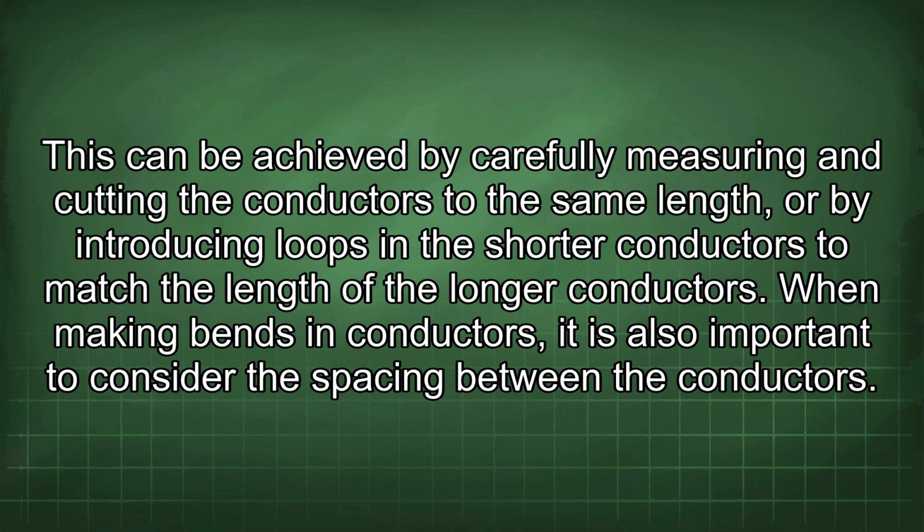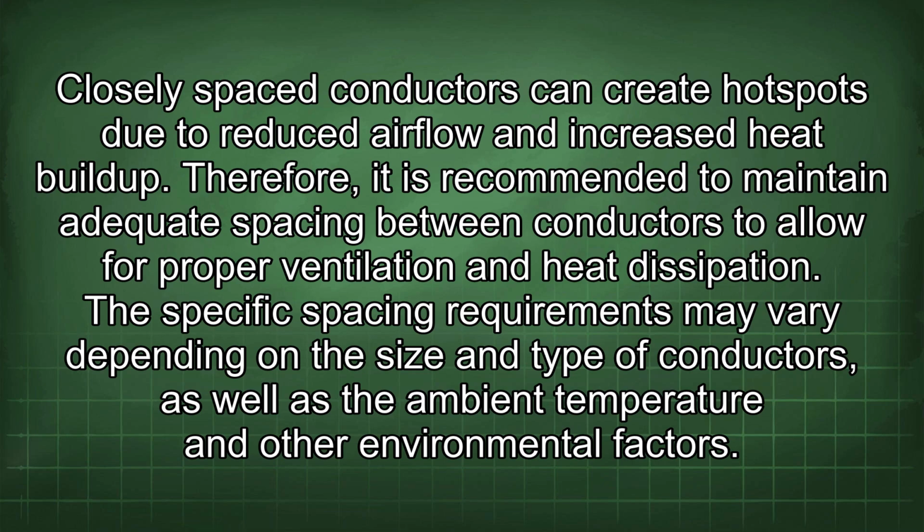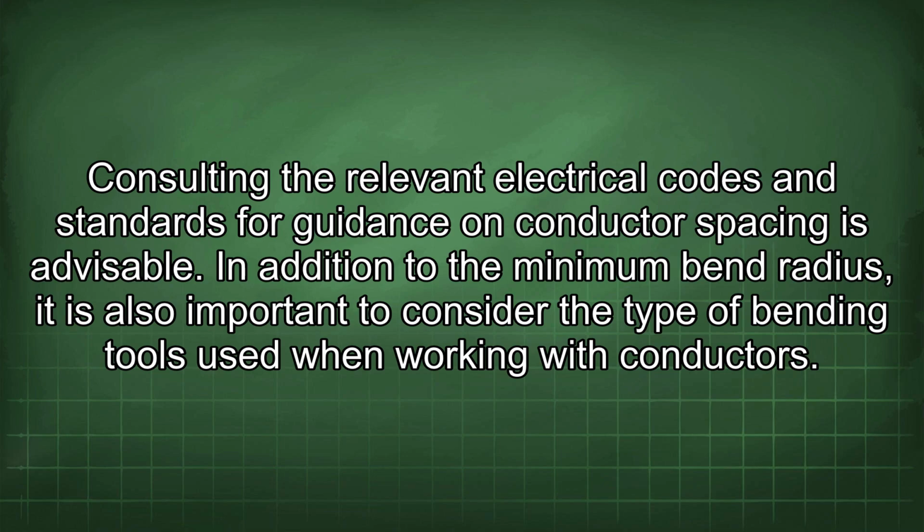When making bends in conductors, it is also important to consider the spacing between the conductors. Closely spaced conductors can create hot spots due to reduced airflow and increased heat buildup. Therefore, it is recommended to maintain adequate spacing between conductors to allow for proper ventilation and heat dissipation. The specific spacing requirements may vary depending on the size and type of conductors, as well as the ambient temperature and other environmental factors. Consulting the relevant electrical codes and standards for guidance on conductor spacing is advisable.